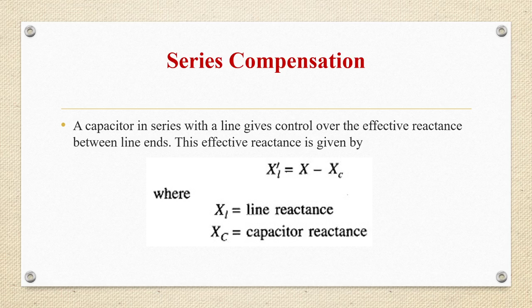Okay. So capacitor which is connected in series with the line will give control over the effective reactance between two line ends, and the effective reactance is given by XL dash is equal to X minus XC. So it is easy to see that capacitor will reduce the effective line reactance. So this will result in improvement in performance of the system as below. Okay, what are the improvements in the performance of the system? Let us now see. So voltage drop in the line will reduce, or it will get compensated. That is minimization of end voltage variations.